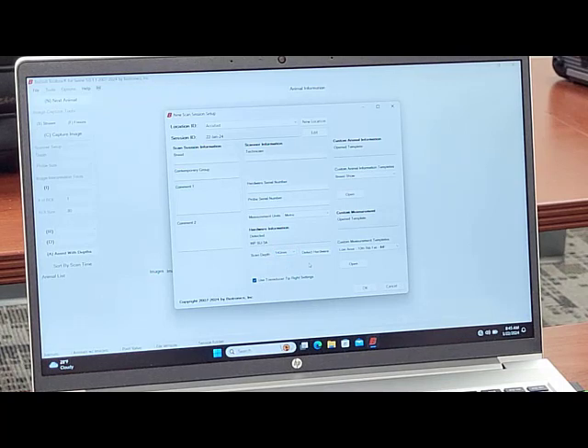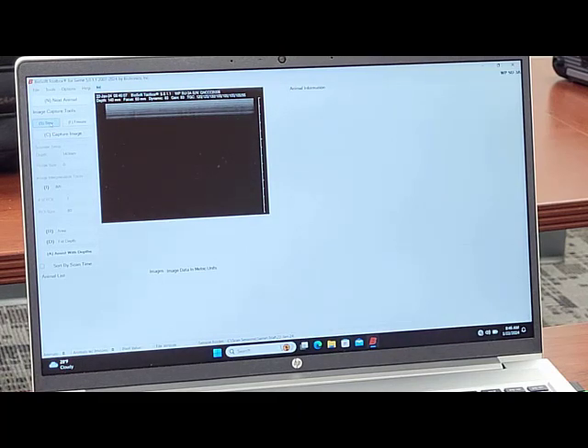Let's go with trial here, and then we're going to open that up and start to stream. You can see that the image has started to stream to the software, and it works exactly like any other ultrasound that we hook up to this. Once you've established that connection, you can capture images from the buffer. If you're scanning an animal and push freeze, you can see that this progress line here has started, and you can scroll back through if you need to.